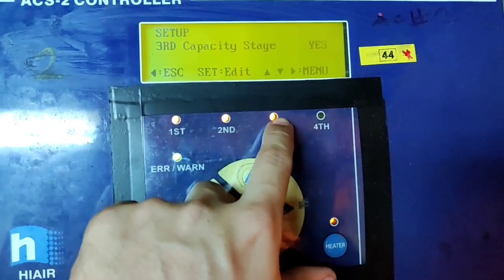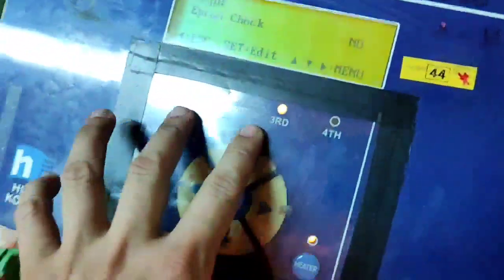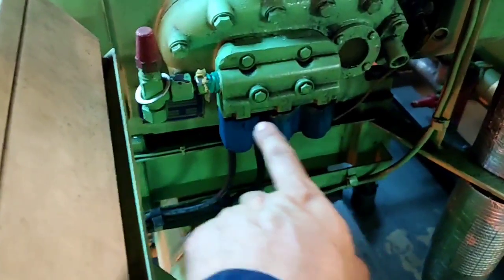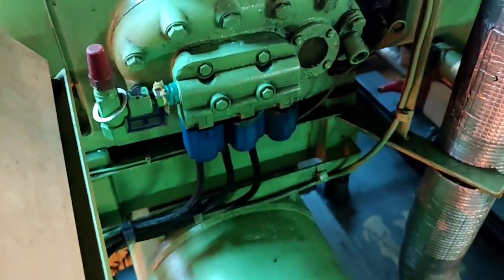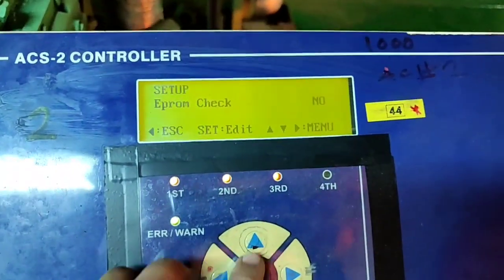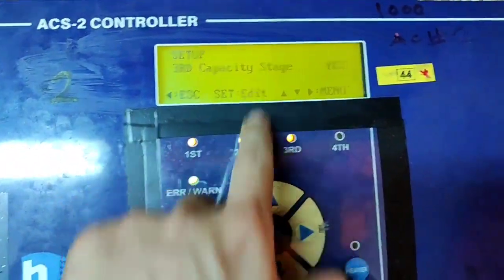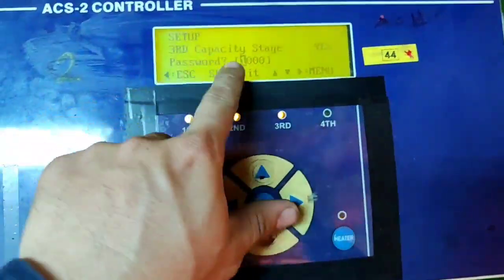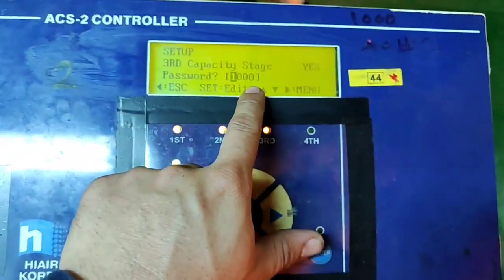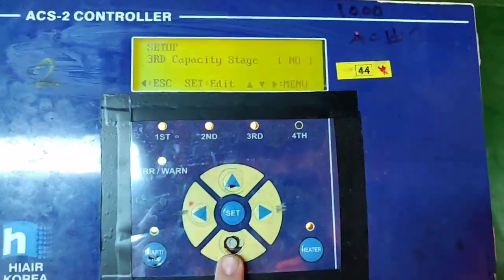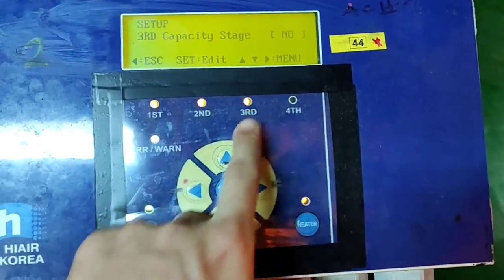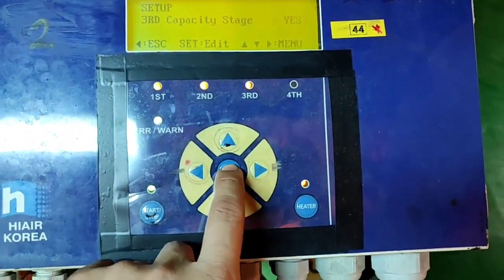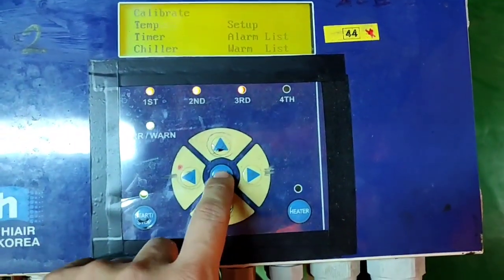Third stage, for example, you want to remove or decrease the third stage. We have only three, three solenoid valves for our capacity: first stage, second stage, and third stage. Sample third stage, just press set and then enter the password and then you can edit. 1000, that is the password and enter. Then up and down if no. Can select no, just press set to remove the capacity.